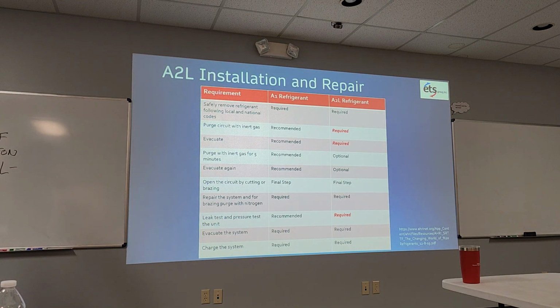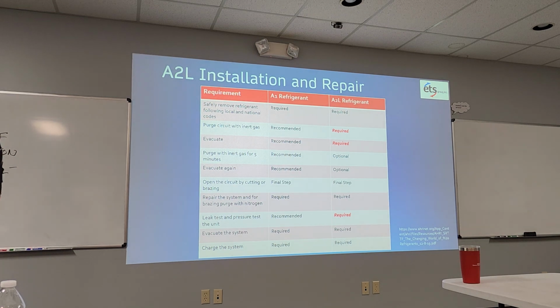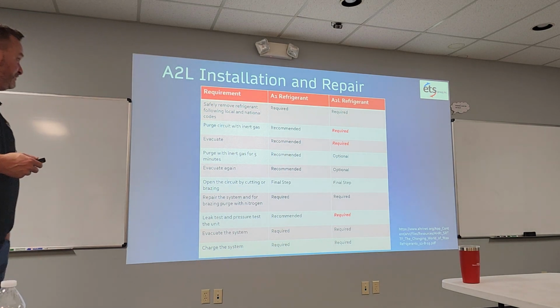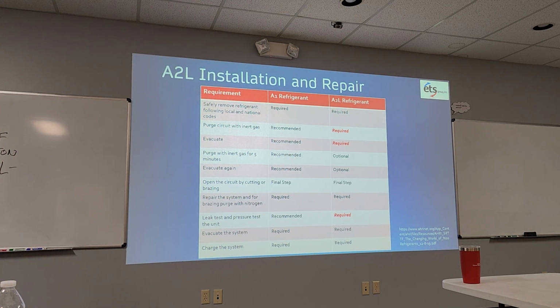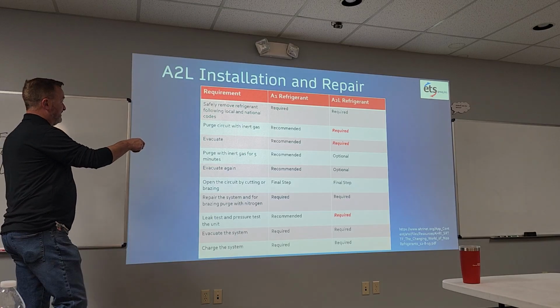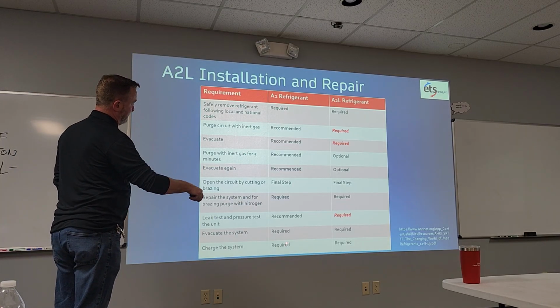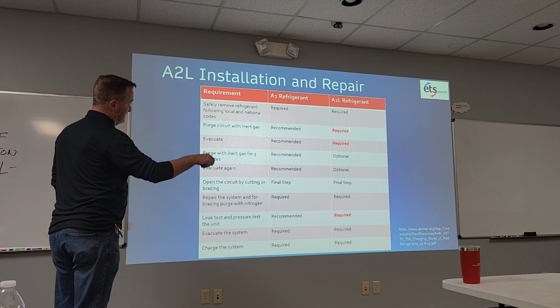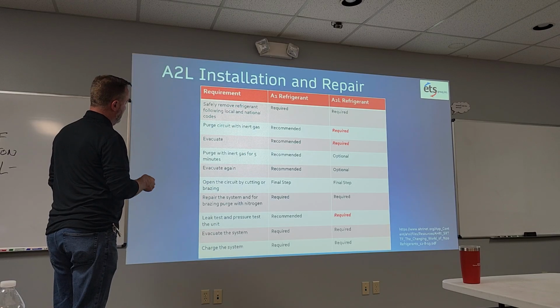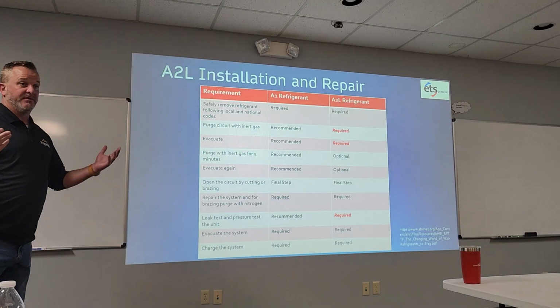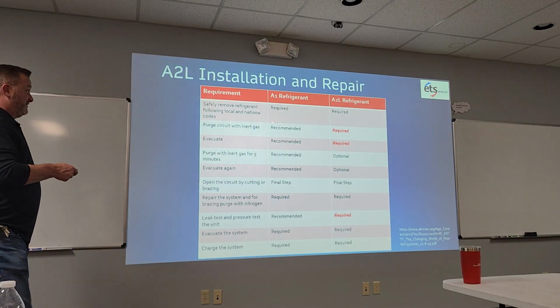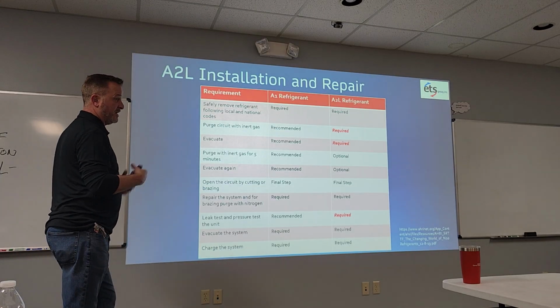So a couple new steps added versus what we were doing with 410A. A2L installation and repair. We're going to safely remove the refrigerant. I've got the A1s here, this will be like your 410A, and this is going to be your new refrigerants over here. So safely remove refrigerant, meaning recover it, okay? That's required obviously on 410A, and it's required on this too. So we're going to recover the refrigerant.